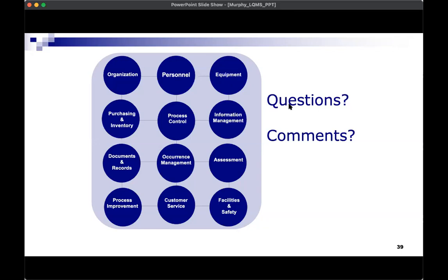One, I guess you said you don't have a temperature monitored box, but one thing you might be able to do is procure an internal temperature probe that can record the temperature of the environment. It's usually just a little probe that you stick in and it'll measure the temperature in the box and record. And then you can look back at those recordings and make sure the temperature didn't rise above a certain temperature.